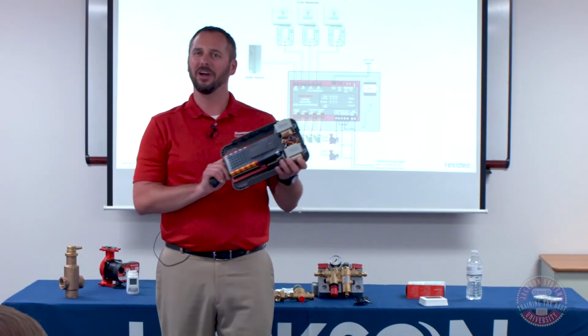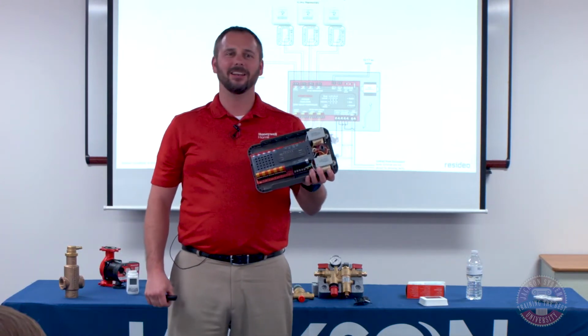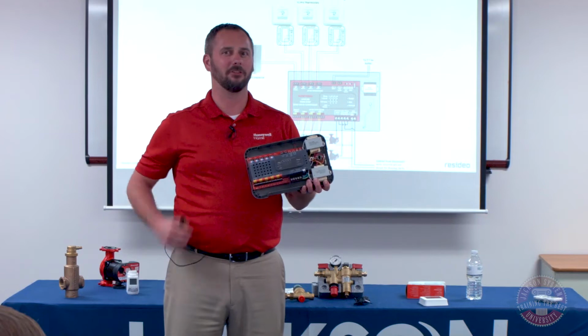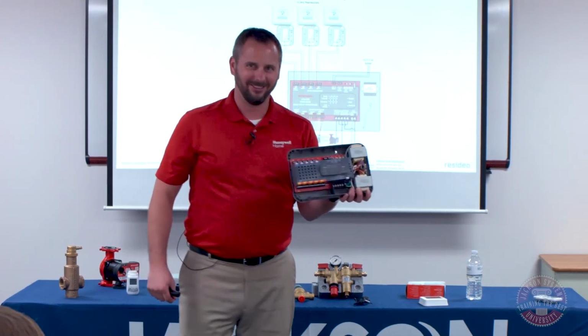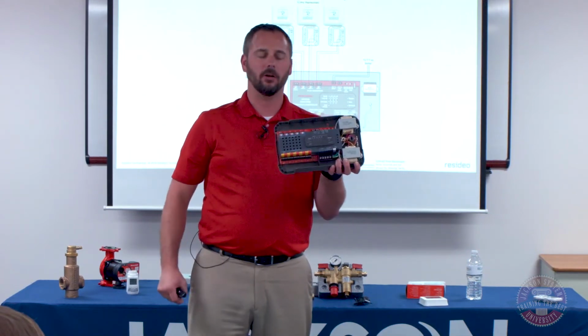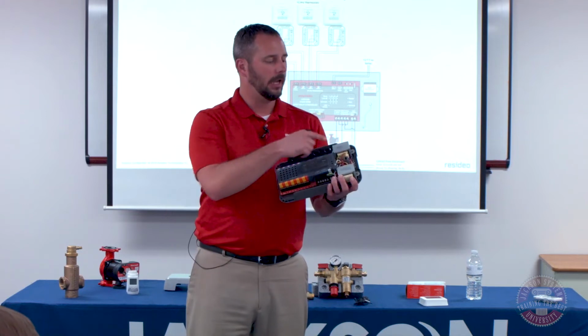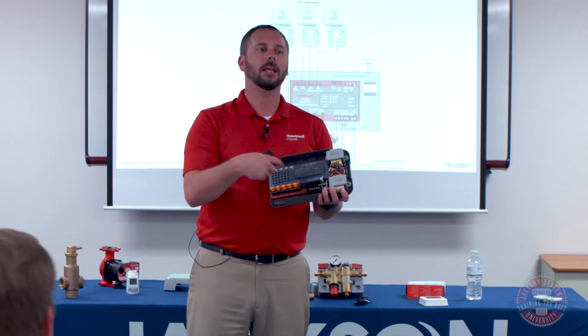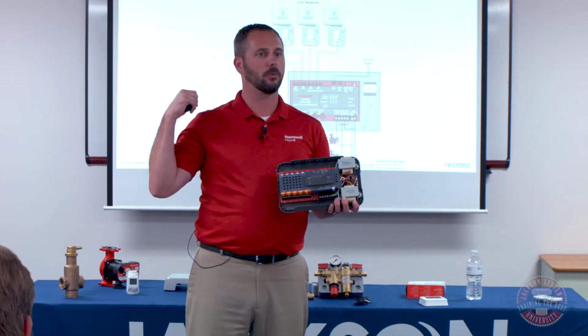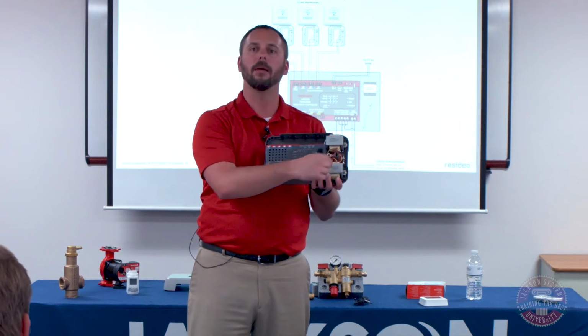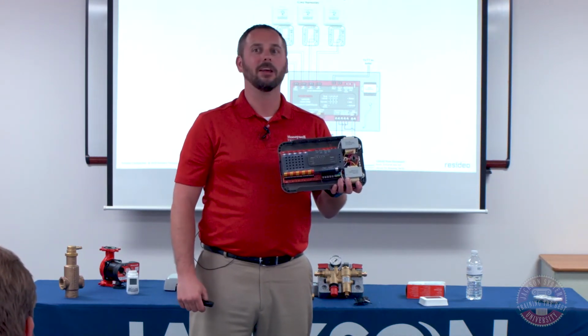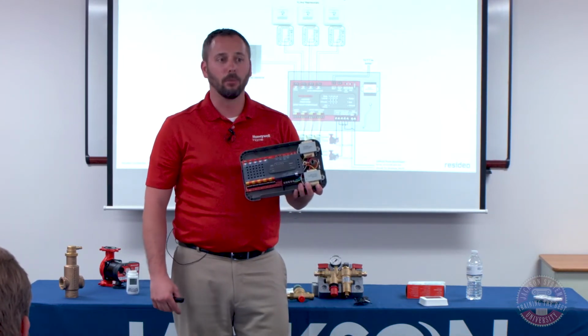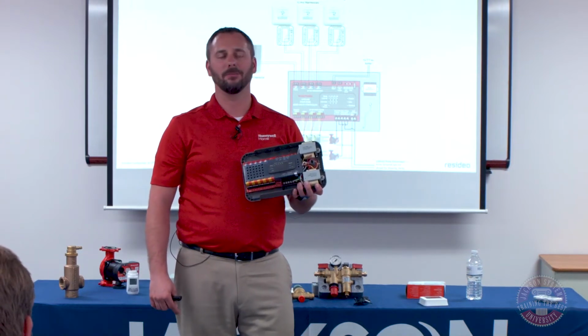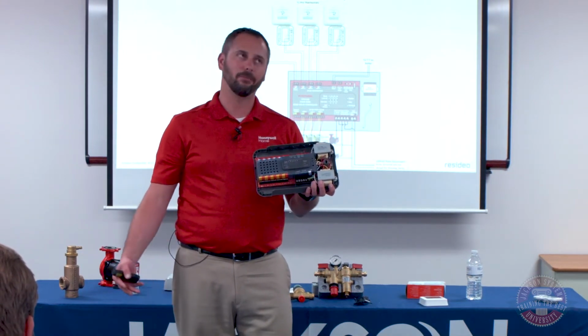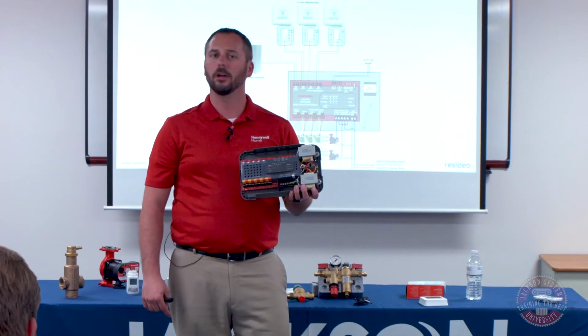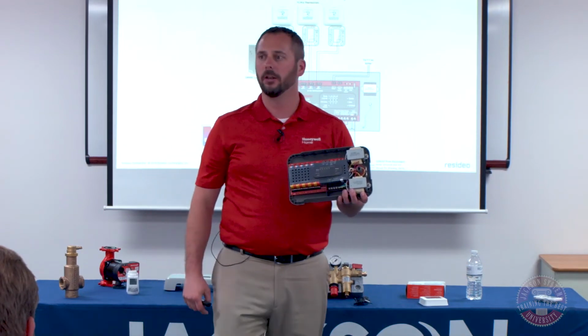I have been guilty, I'll go ahead and own this one, of wiring things incorrectly and hearing the good old pop and then smelling the smoke that I let out of the transformer. If you do that with this, we have additional fuses packaged in the casing. And these transformers, we did them with wires so that in case you do blow a transformer, if you've got a universal 40 VA transformer on the truck, you can bring it out, screw it right next to it, and wire it right back in where the one that doesn't have any smoke left in it is. So there's no need to replace the entire board because you blew a transformer. So with that being said, if you did something catastrophically wrong and you fried the circuit board, that is possible, but 9 times out of 10 it just ends up popping either a fuse or a transformer. So you've got the ability of kind of getting this thing back up and running in the field.